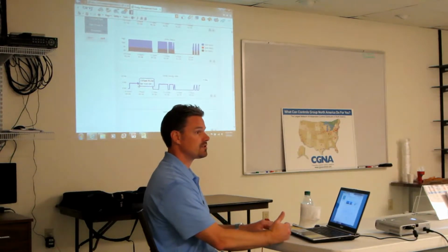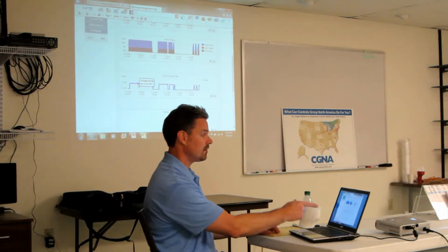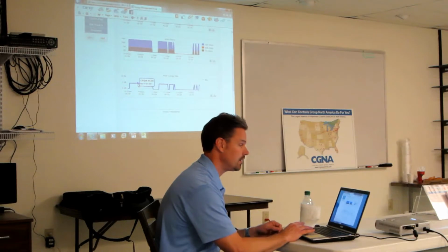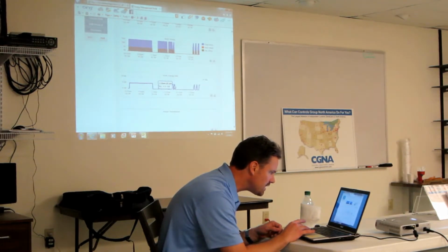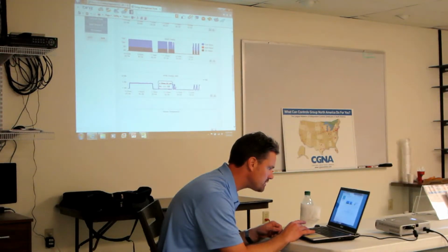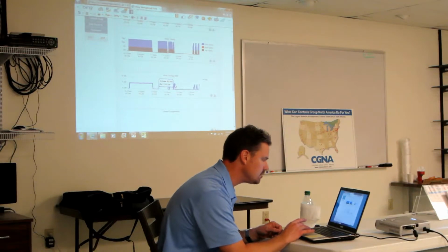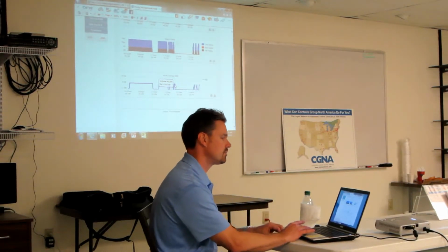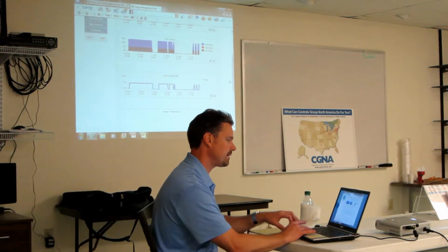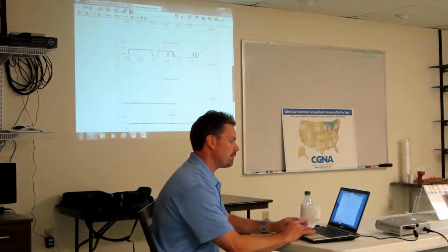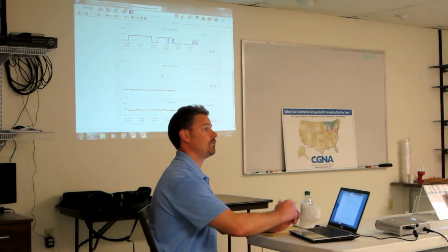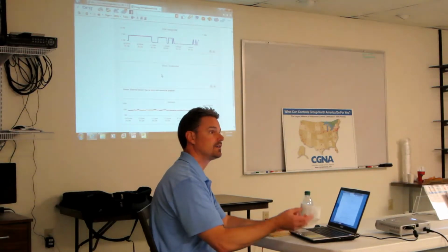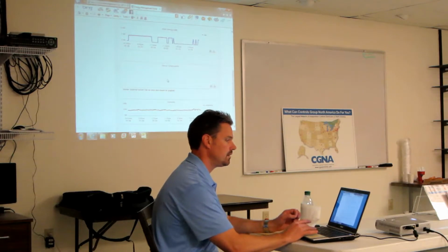So if it's a bad compressor and it's not coming on, then you're not going to see the compressor energy here. And then, by the way, you can see the difference between a stage 1, a little more than 2.6 kW, and then a stage 2 call, and how much energy those draw. That's a small unit, it looks like. If they're using an external temperature sensor, that would be graphed here. So, for example, if you're using one in supply air, that would be graphed in here.